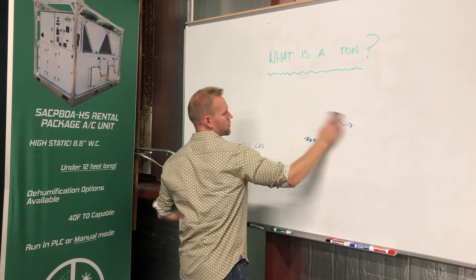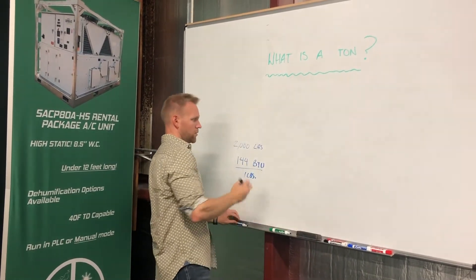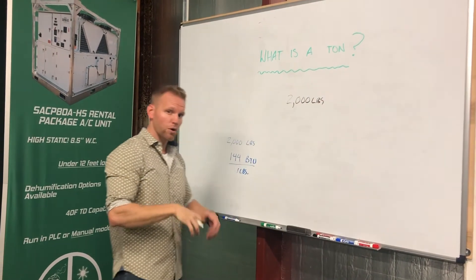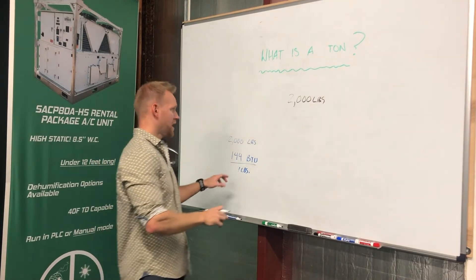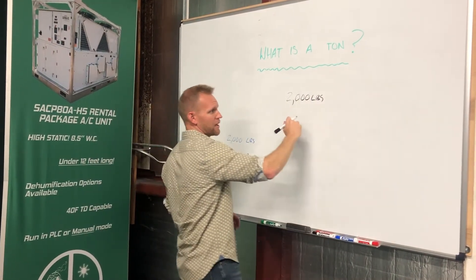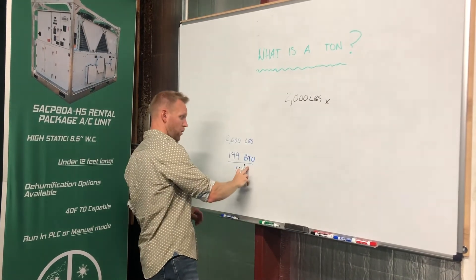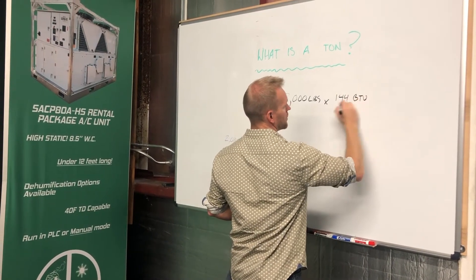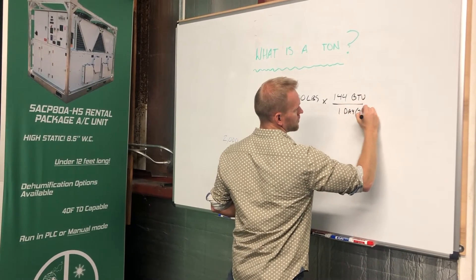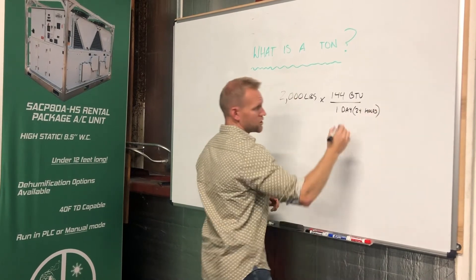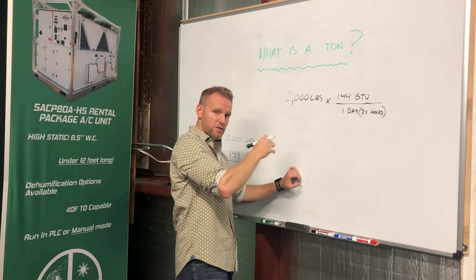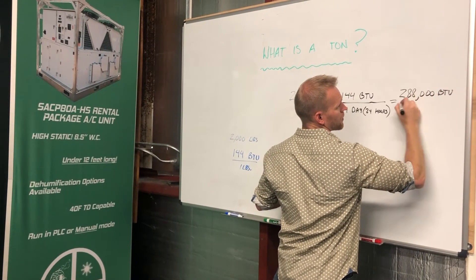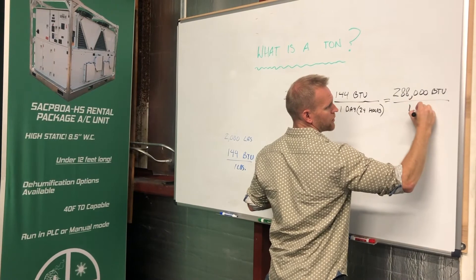So how do we come to the ton as we know it today? Let's walk through the process. The term comes from the energy required to melt 2,000 pounds of ice over a one-day period — that's the standard. We know we have 2,000 pounds of ice and the energy required to melt one pound of ice is 144 British thermal units. So we multiply 2,000 by 144 to get the total energy required to melt one ton of ice in one day, which equals 288,000 British thermal units per day.